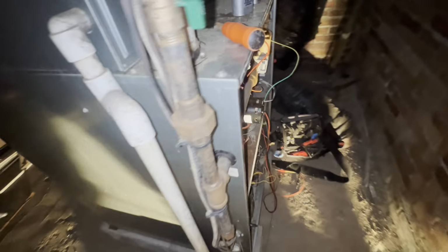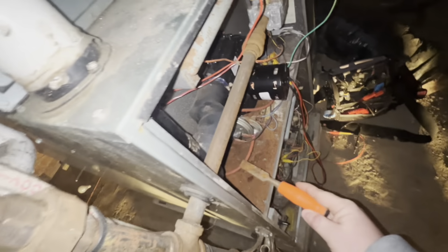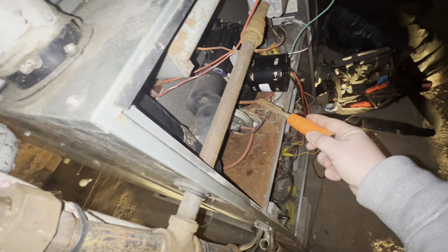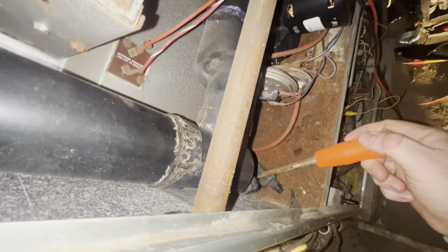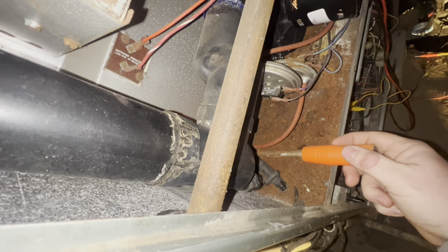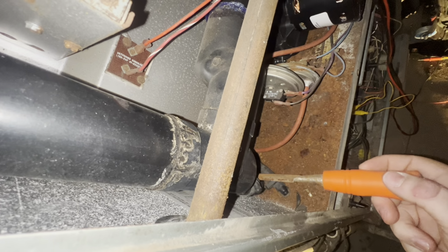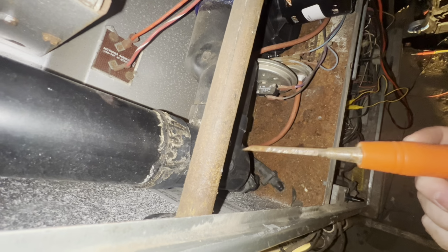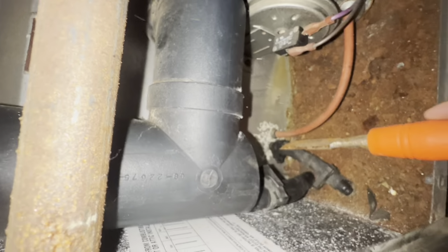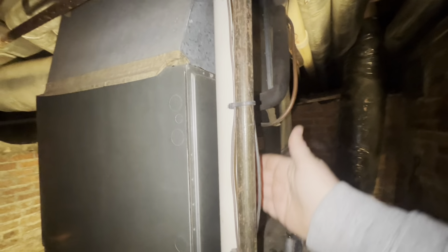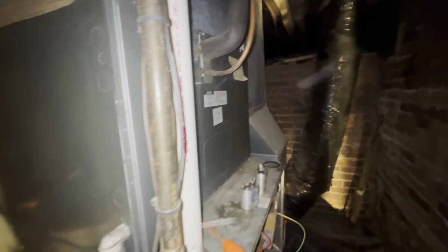So at this point in time, what we've done is we've pulled this tubing right here, blew through it, made sure we have no clogs. We also pulled these drains off. Very easy to do. They just come straight off of there. I blew through the drain that collects from the exhaust pipe right here. And I pulled this drain off right there. Blew into that guy, making sure that we're clear. The last step to check is going to be the exhaust pipe. This PVC vent going all the way outside. So we're going to step outside and take a look at that.